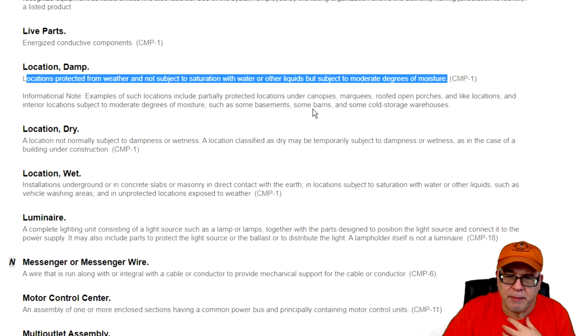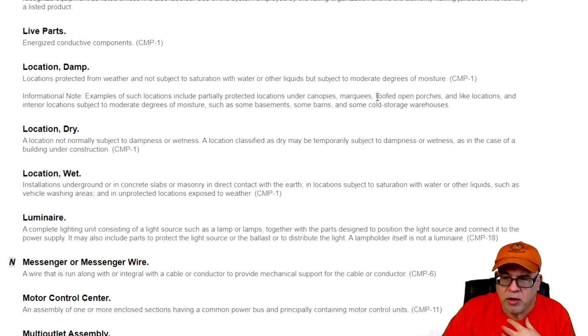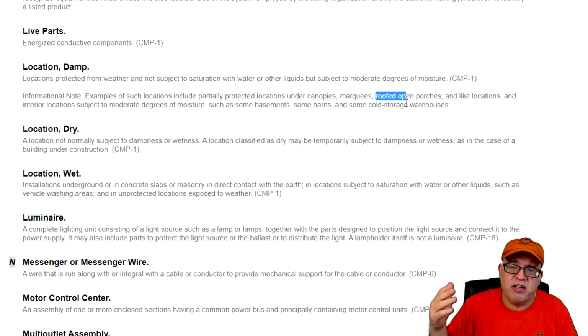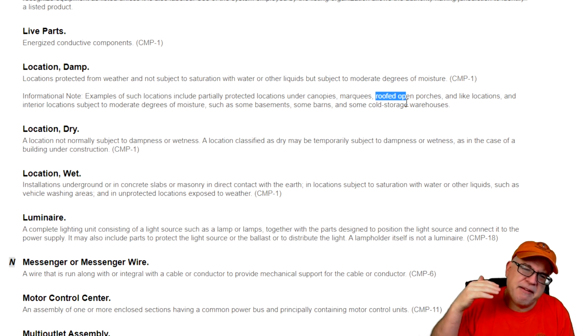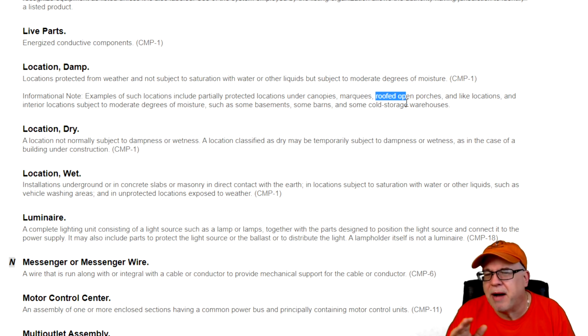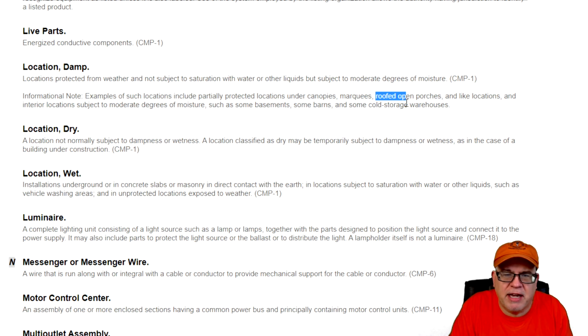A great example of this, and it gives you some examples, is under canopies, open roof porches, which again is not really subject to saturation, but it could be subject to condensation. You could have moisture in the air. Okay, but it's protected directly from the elements. So it is subject to moderate degrees, but it would be easy to say that any open porch or locations like that are subject. But it also could be interior locations that are subject, like basements, crawl spaces, things like that, could be argued that it's a damp location. And then some people could argue, depending on how sealed up the crawl space is, that it's a dry location. Okay? Again, all in the argument.